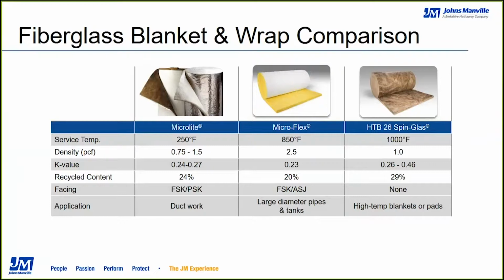Really, it's intended to go on ductwork, and again, for all those other reasons we discussed of energy conservation and condensation control. Microflex, again, more along the pipe side of things. It's going to have a service temperature of up to 850 degrees Fahrenheit. It is one standard density of 2.5 pounds per cubic foot. The K value is right in line with the pipe insulation at a 75-degree ambient installation. It does have some recycled content in it, and really we try to encourage installers to consider this product for even large pipe diameters, not just vessels and tanks, but really pipe sizes of 20 inches diameter and above are great applications for Microflex.